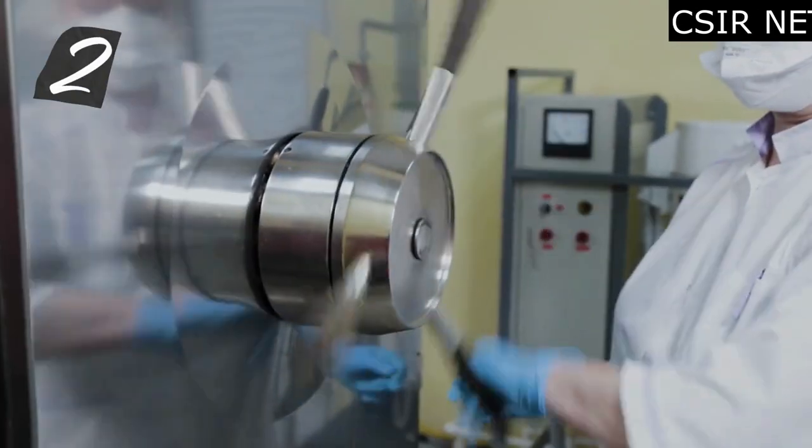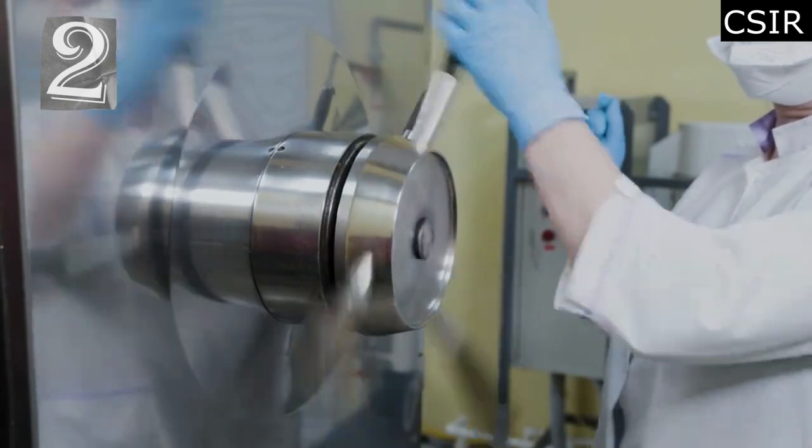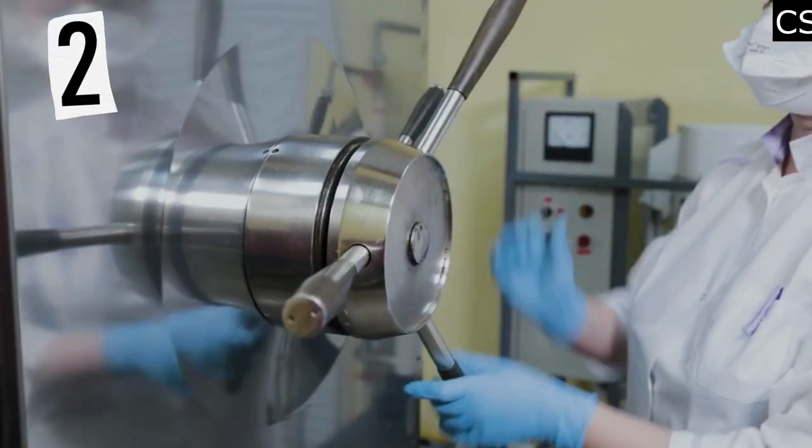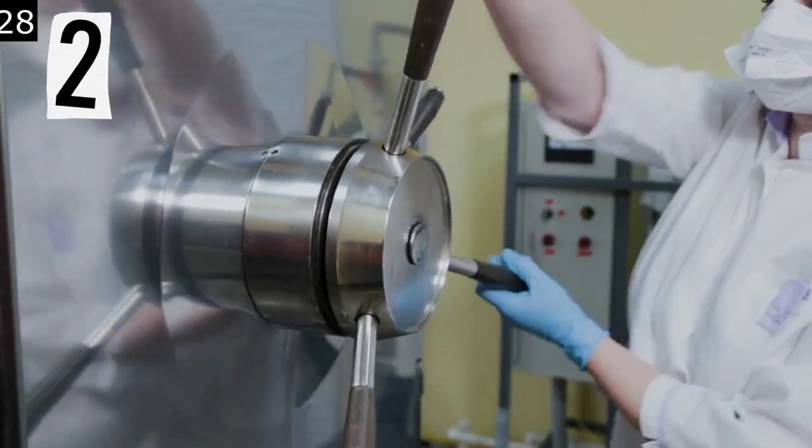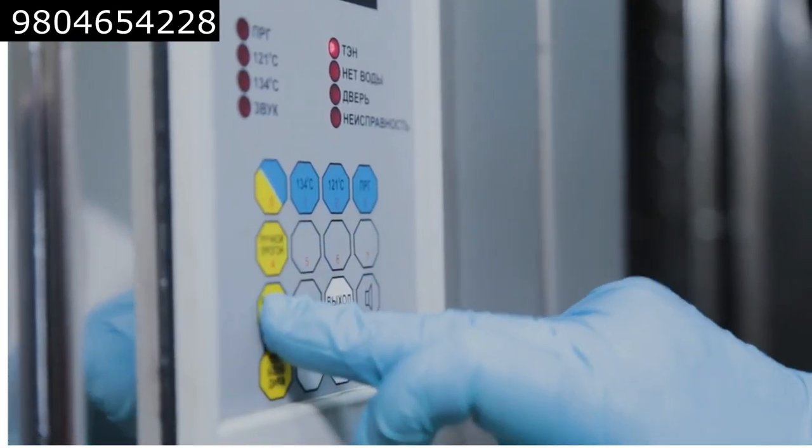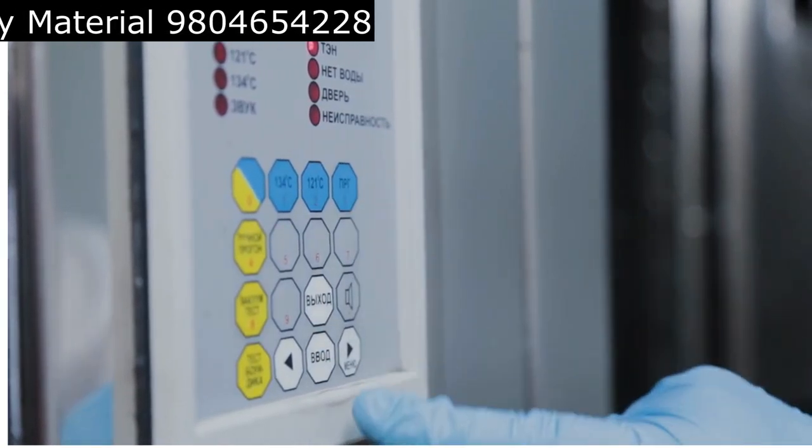Step 2 is setting the sterilization parameters. After loading the items into the autoclave, it's time to set the sterilization parameters. This includes setting the time, the temperature, and the pressure. The appropriate sterilization parameters will vary depending upon the items being sterilized, so make sure to refer to the manufacturer's instructions or guidelines for the items being sterilized.